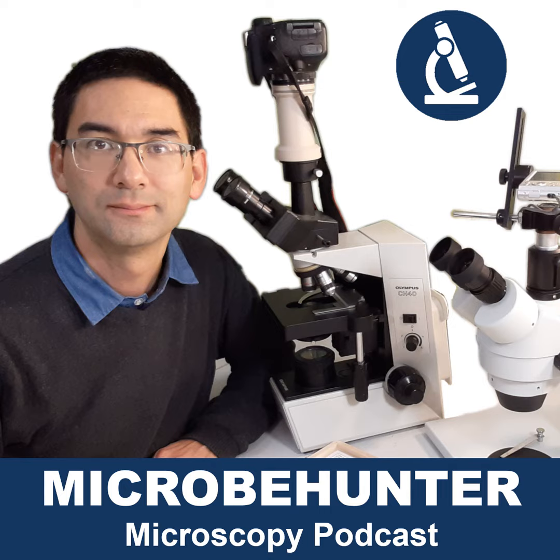If this doesn't work because you're already at the maximum intensity, then you have to go up with the so-called gain of the camera. Basically you're increasing the camera sensitivity, and there should be a setting somewhere in the software where you can adjust the gain. So you just put the gain level up, and this makes the image brighter again, with the unfortunate side effect that the image noise, the image grain, will also increase. Okay, but still you want to go with a fast frame rate, maybe 30 frames per second, and also a fast shutter speed.